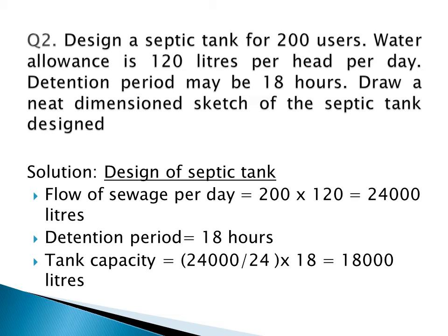The second step is the detention period, which is given in the question as 18 hours. If it is not given, you can assume a value between 12 hours to 36 hours. The third step is to find out the capacity of the tank. For a detention period of 18 hours, the capacity equals 24,000 divided by 24 multiplied by 18, giving 18,000 liters.